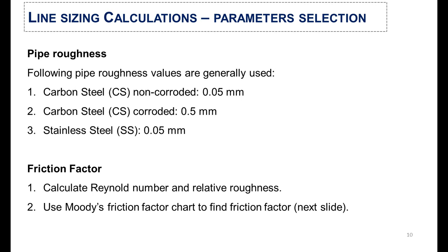For the Moody friction factor, you need to select a few parameters. First, you select the pipe roughness according to your material. If your material is carbon steel, you select 0.05 for non-corroded and 0.5 for corroded. For stainless steel, you select 0.05 as the roughness. After that, you calculate the Reynolds number and relative roughness, then use the Moody friction chart to find the friction factor.